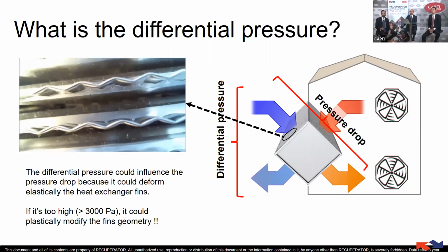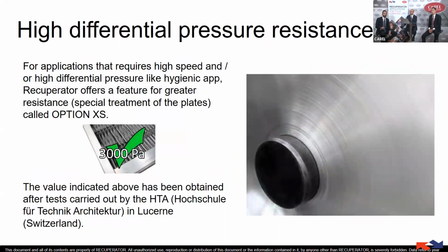This is important because in hygienic applications, mainly hospital applications, we can have really high velocity and also a great difference between two different environments. That means we need a heat exchanger that is able to face this high differential pressure, because if it is too high, we can also have elastic deformation.